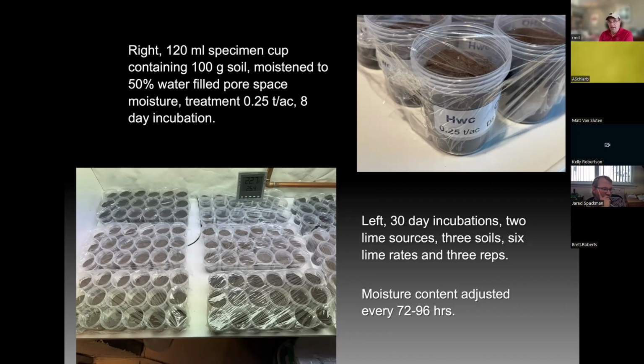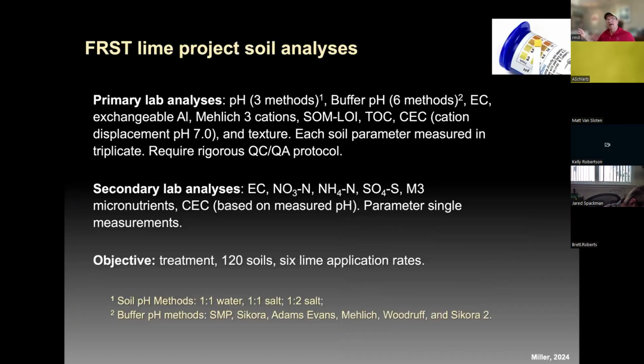I anticipate that we're going to find calcium hydroxide is going to work the best in a 4 to 8 day time frame. So we feel 4 to 8 days is going to minimize the amount of nitrification that we're going to get relative to a time frame of 60 days. When we come back from this pilot study, we're going to launch into the major study.